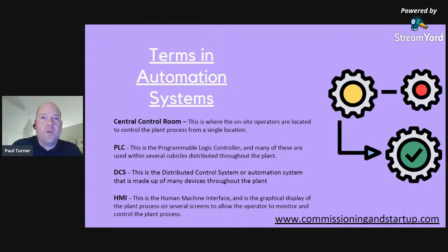The alarm screens, that's a very important portion of the HMI system that the commissioning team will want to pay attention to. The alarm screen is really all the statuses from the system, and as you're going through and commissioning the systems, the alarm screen is probably the first thing that you're going to be paying attention to confirm that you're getting the right responses from the end devices and they're alarming at the right levels for high or high-high alarm points. The alarm screen is something definitely to pay close attention to during commissioning, because that's really the operator's main alerting portion of the HMI system to know if there's components within the plant that need to be addressed. And it needs to be accurate.